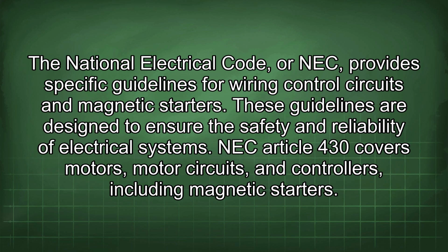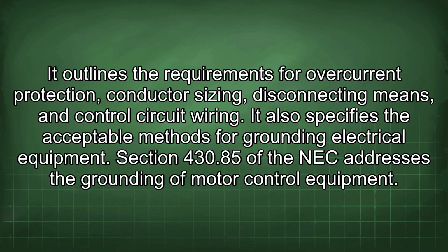The National Electrical Code, or NEC, provides specific guidelines for wiring control circuits and magnetic starters. These guidelines are designed to ensure the safety and reliability of electrical systems. NEC Article 430 covers motors, motor circuits, and controllers, including magnetic starters. It outlines the requirements for overcurrent protection, conductor sizing, disconnecting means, and control circuit wiring. It also specifies the acceptable methods for grounding electrical equipment.